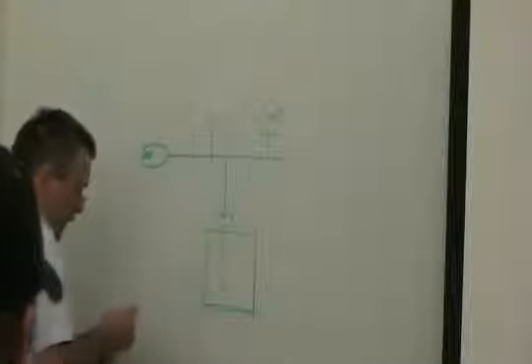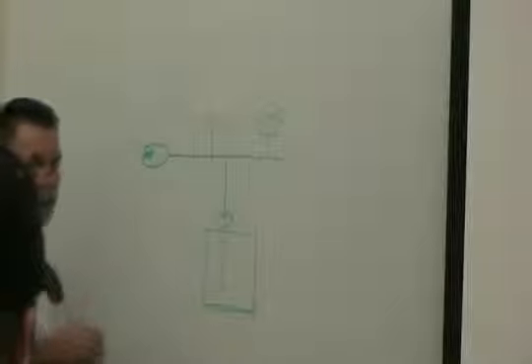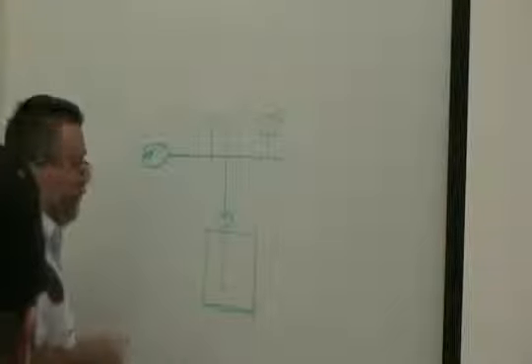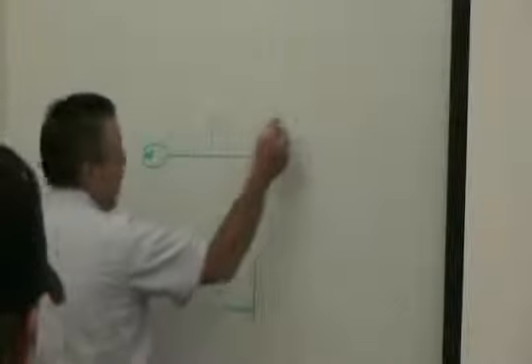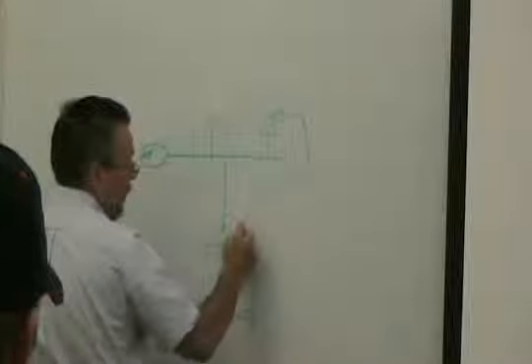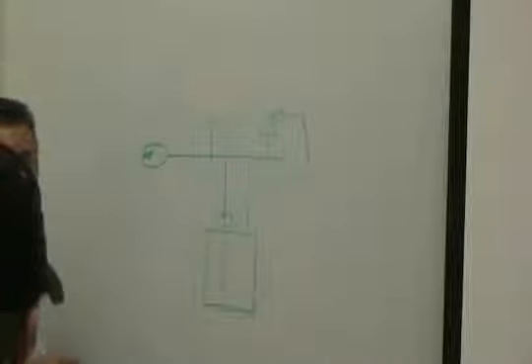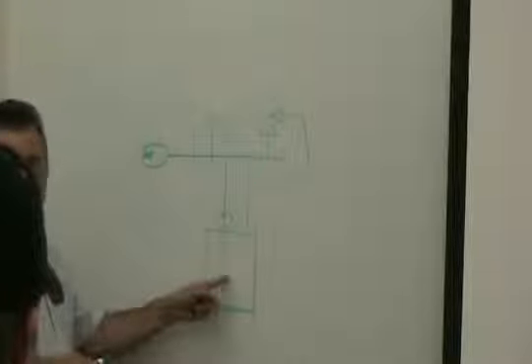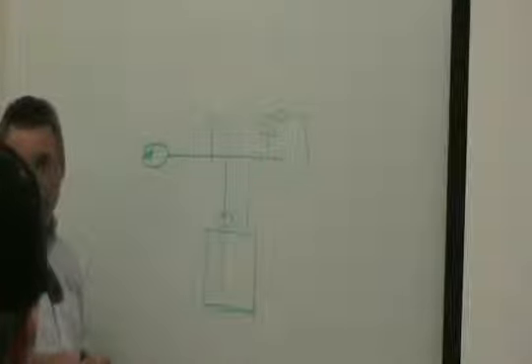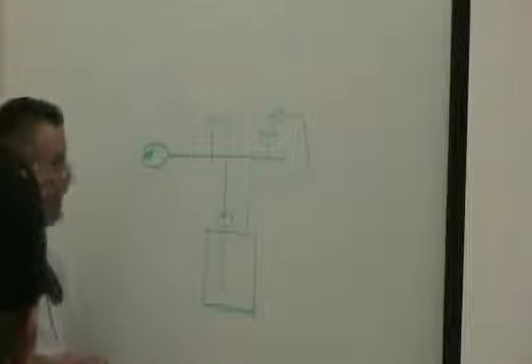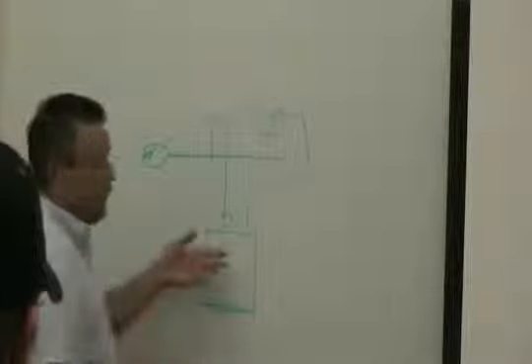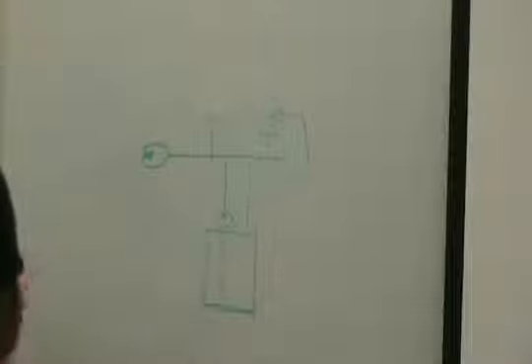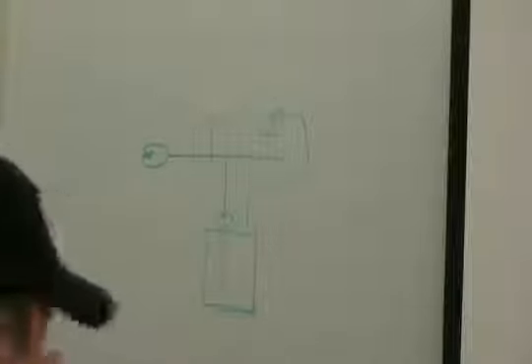But you can put a backflow preventer on a glycol system and have a direct connection. Most people don't. And then this relief valve here actually drains into the tank. Is that very common? It's expensive, so I'd say no. I haven't seen one. The alternative is you just lose your glycol if you release water. We just put one in out there.